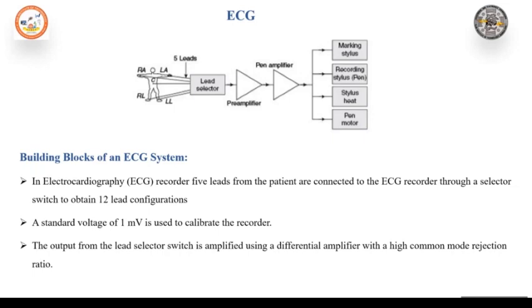The potentials picked up by the patient electrodes are taken to the lead selector switch. In the lead selector, the electrodes are selected two by two according to the lead program. By means of capacitive coupling, the signal is connected symmetrically to the long tail pair differential preamplifier. The preamplifier is usually a 3 or 4 stage differential amplifier having a sufficiently large negative current feedback from the last stage to the first stage, giving a stabilizing effect.